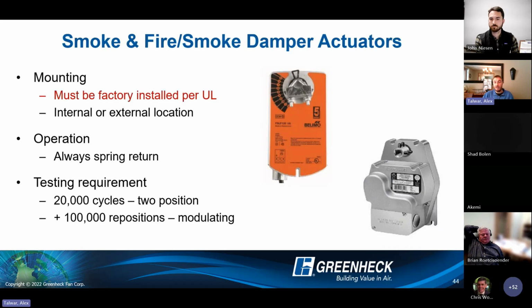But the actuators, these are very important with smoke and fire smoke dampers. The actuator model is tested with the damper model. So we'll have certain combinations of actuator models that we can use with certain combinations of damper sizes. They have different torques, different performances, all that kind of stuff. Again, we are testing them as a unit. So they're both subjected to that heat test as well, 250 or 350 degrees. So even if it's an external actuator, we'll put an oven box around it, heat the actuator as well, and make sure that thing can function under heated conditions.